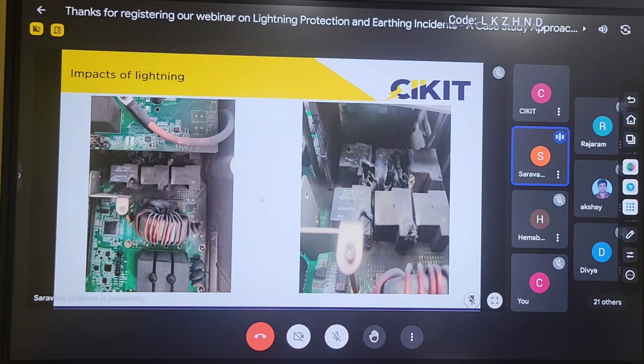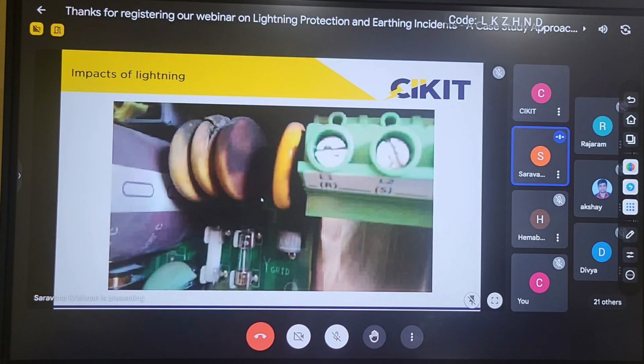We have worked with certain projects where, even for residential buildings, they have provided a separate surge protection device for each and every panel room for protecting the electronic equipment. In one project they had procured a TV for almost 14 lakhs. They waited for 1 week for installing the surge protection device, and only after that did they turn on the TV. So if we install surge protection devices, these kinds of damages can be avoided.